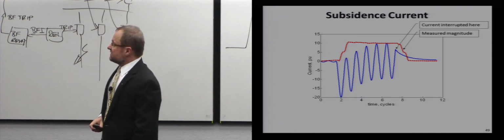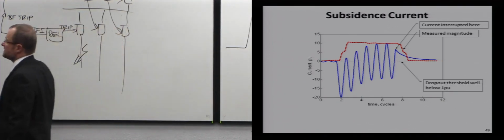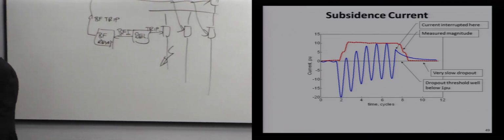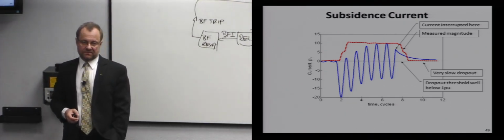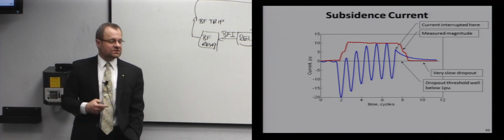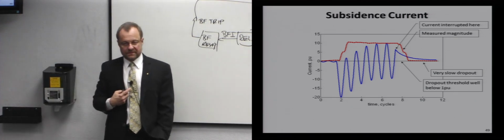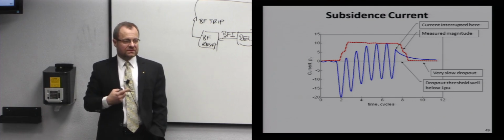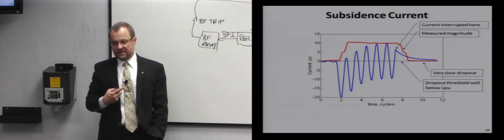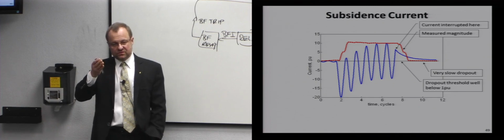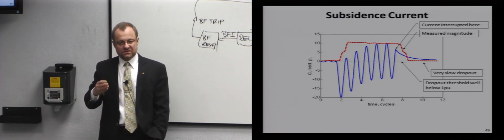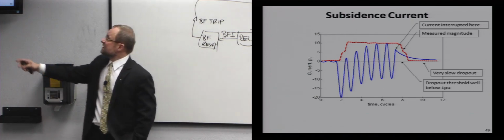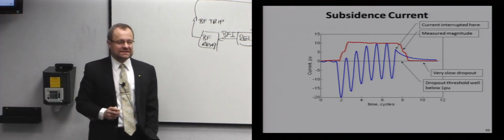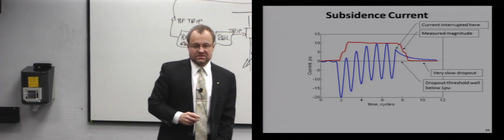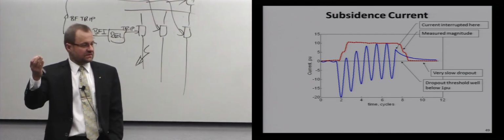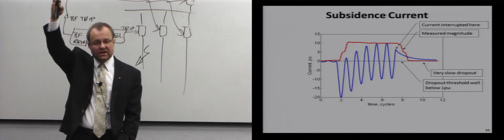Now, the difficulty here is that the threshold to declare the current gone is very, very low. This threshold in many applications would be below the load current. Assume that it's equal to a load current, so roughly 1 per unit, right? So this is the line that we have to go below for this element to drop out. But what is our starting point? Our starting point could be 20 per unit, because the fault current could be 20, 25 times nominal. So we have a long way to go.